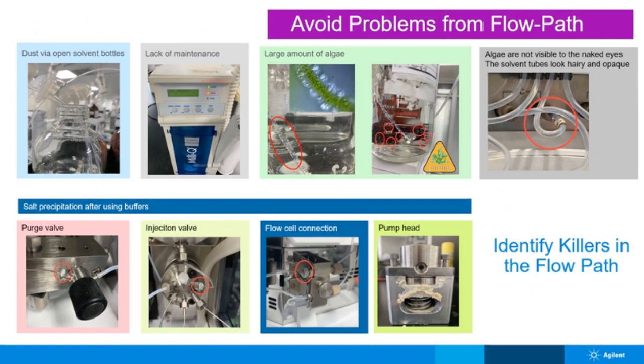On this slide, we can see typical issues in the flow path and how they look like in reality. Dust via open solvent bottles, algae growth, salt precipitation at different areas in the flow path, like on the purge valve, on the injection valve, on the flow cell, or on the pump head.